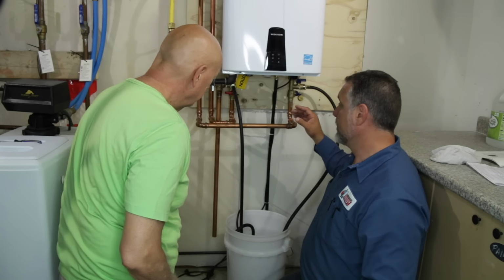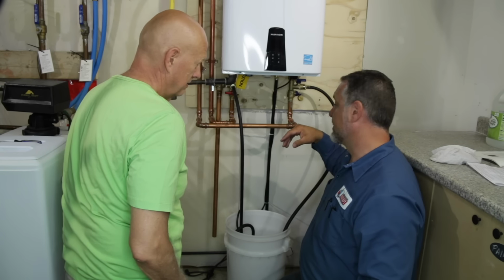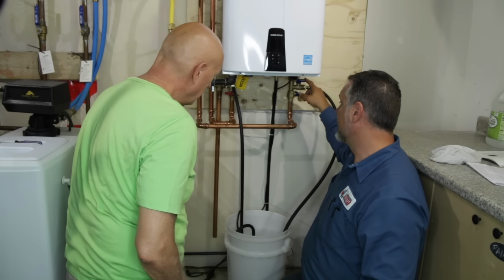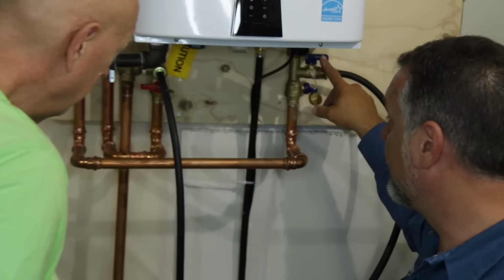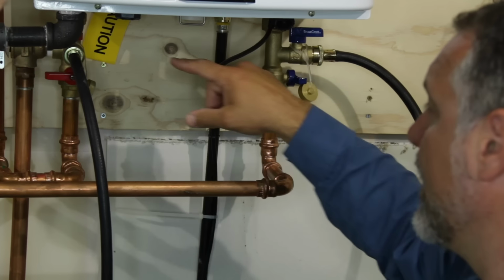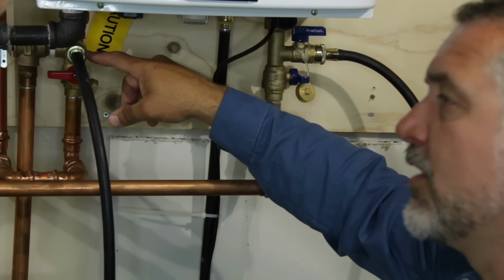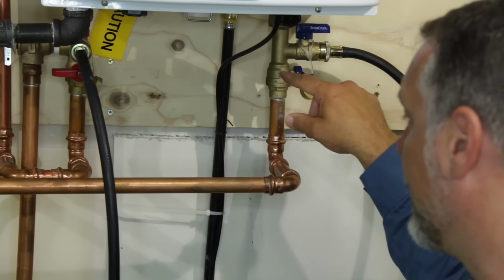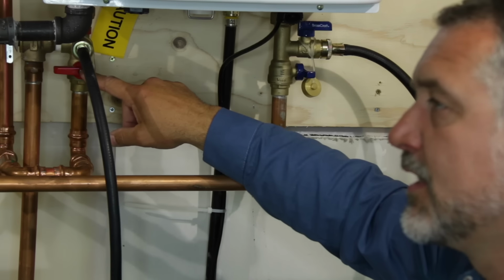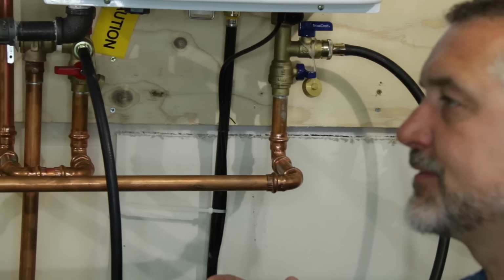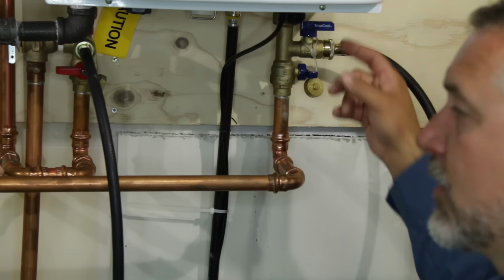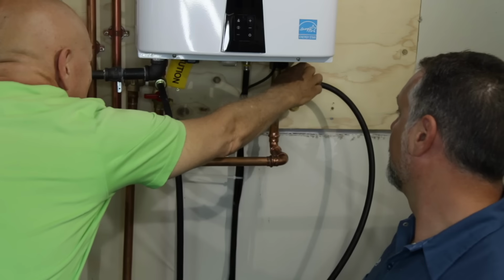Now what we're going to do is purge the vinegar out of the system. The way we're going to do that is turn off this valve, the service port valve. The upper blue and red valves are called service port valves, and the lower blue and red valves are the main shutoffs for the hot and cold side. So go ahead and shut the cold service valve off.